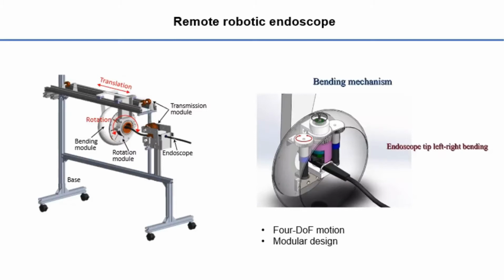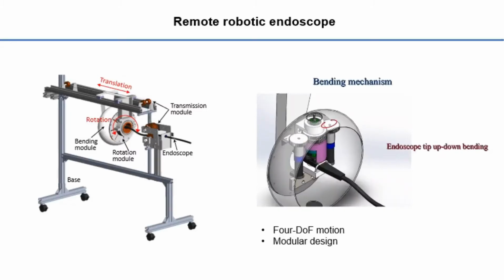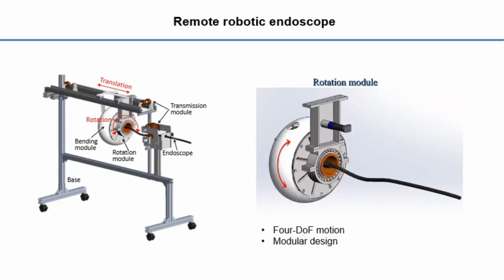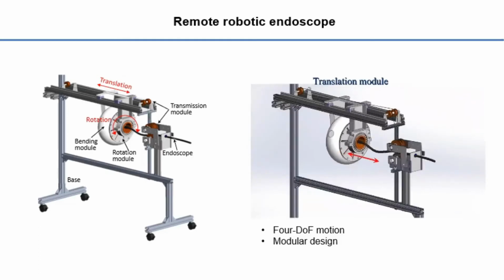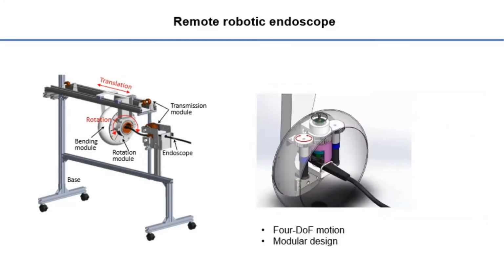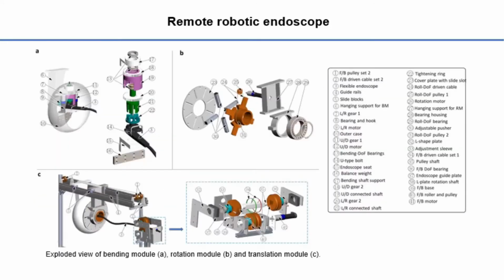They are a bending module controlling the two-degree-of-freedom bending of the distal tip, a rotation module implementing the rolling degree of freedom of the whole endoscope, and a translational module conducting the in-and-out translation of the endoscope. The exploded view of the remote robotic endoscope with three modules is shown in this slide. Please see the paper for more detail on the mechanical design.